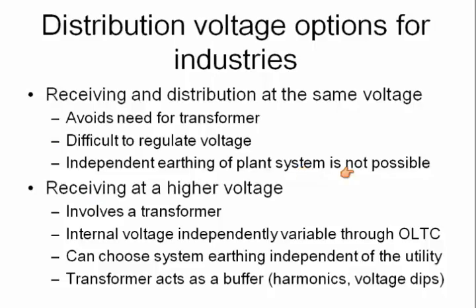On the other hand, you have another option which is more expensive but might save you in the long term. Receiving at a higher voltage, then use a transformer with an on-load tap changer to control the voltage. You can have independent earthing, independent of what the utility does. The transformer acts as a buffer for harmonics or voltage dips. So receiving at a higher voltage, then you are stepping it down. For bigger loads, bigger plants, you use this arrangement.